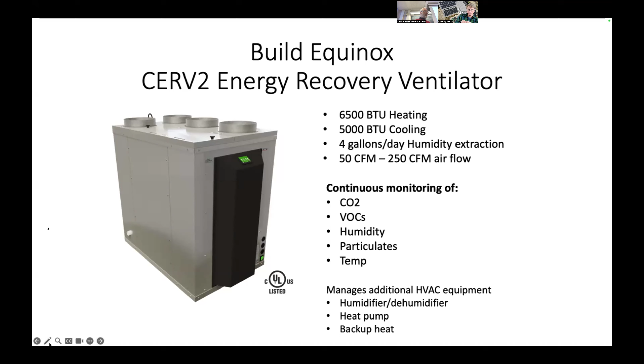This has sensors in the exhaust going out that continuously monitor CO2, VOCs, humidity, particulates, and temperature. And it also has additional control options for running an external humidifier and or dehumidifier. It can manage additional heat pumps or backup heat. If I want to fire up the old propane furnace or I want to install electric resistance, this unit will be the brains that manages all of the indoor air quality.